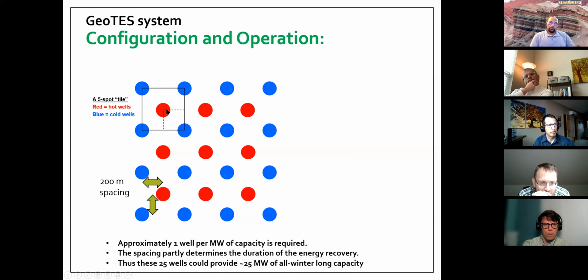Now, to date, unfortunately, all of the reservoir modeling has been incorrect. This is not a valid model for a 5-spot with a thermal resource. The reason is that this would be valid if the volume coming out of the cold wells was the same as the volume going into the hot well, and vice versa on the discharge cycle, but it's not.